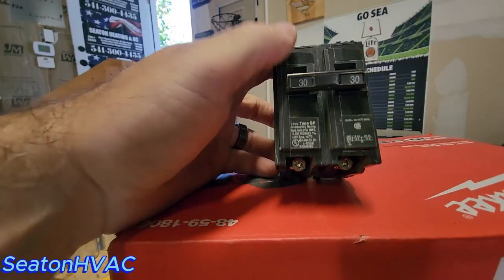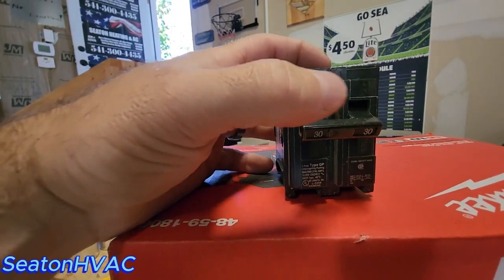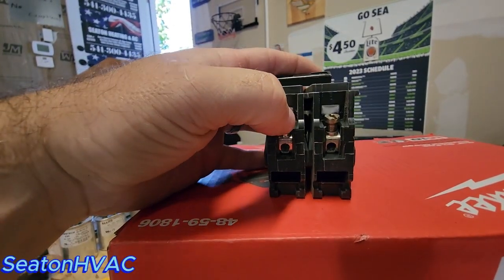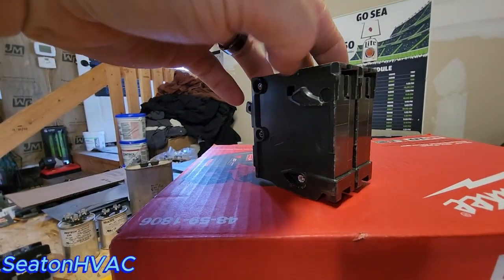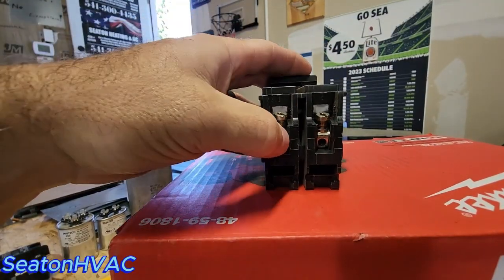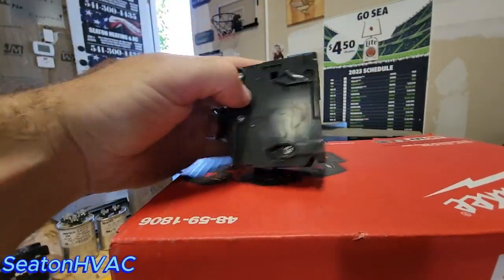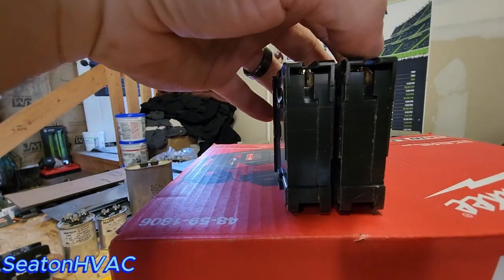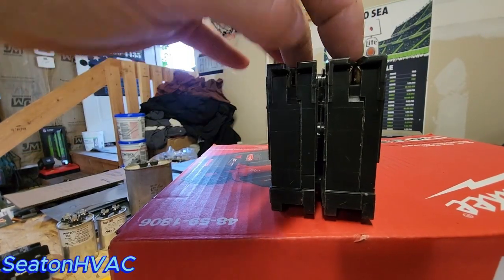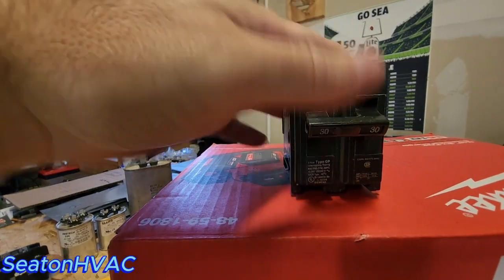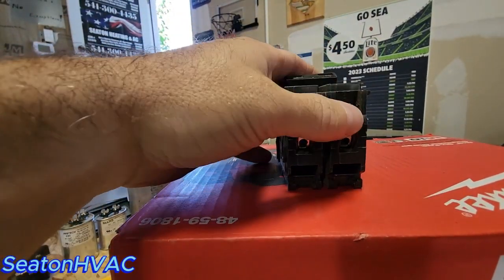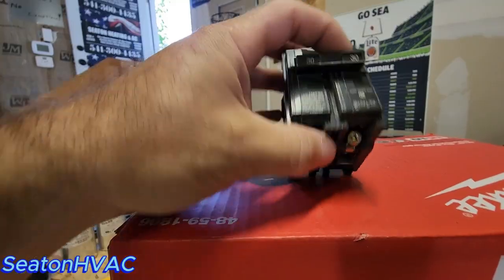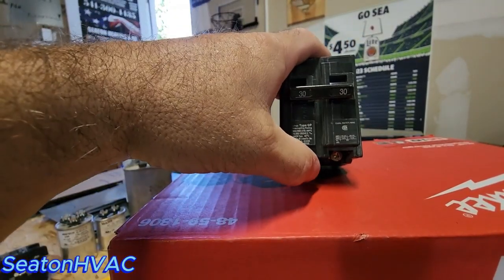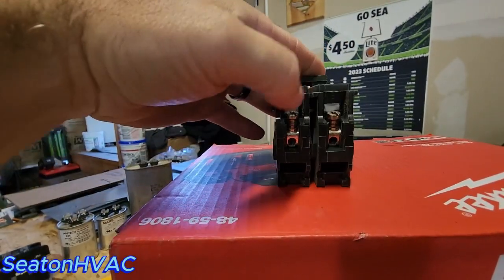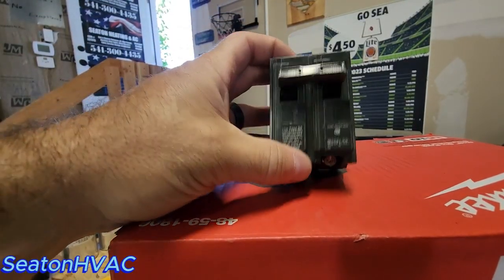So, this is a 30 amp. See the 30s on there? It's a 30 amp two-pole breaker. So you've got your 120 volts here, your 120 volts there, 240 volts. When you flip this up, you now energize these terminals. When this is down, the teeth that go into your breaker panel are 120 volts here, 120 volts there, 240. With this down, you're broken to your terminal, so you can work on it or test it. Let's say you've got your meter on there and you flip this up, you should have 240 volts here. If you do not, you've got a problem with this breaker.